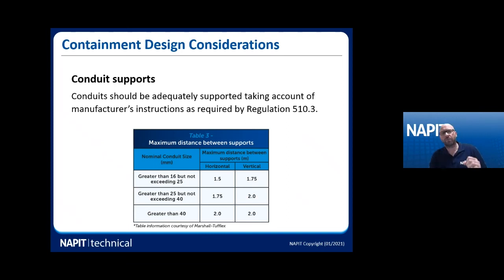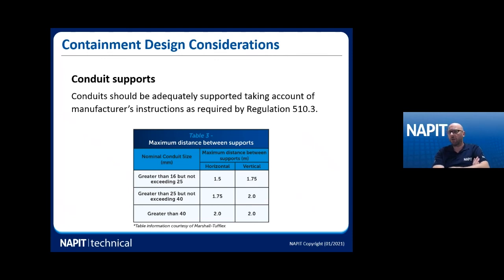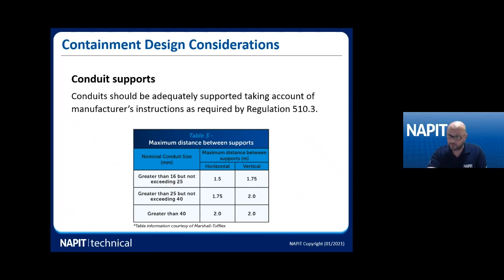We also need to look at conduit supports, which were mentioned in the requirements of Chapter 52. We often turn to manufacturer's requirements to meet regulation 510.3. For example, for conduit sizes between 16 and 25mm, the maximum horizontal support spacing is 1.5 metres. Remember these are maximum distances — you'd likely get some sag at 1.5m with a plastic conduit, so you'd probably want more supports than the maximum, but these are the manufacturer-supplied maximums for this particular conduit.